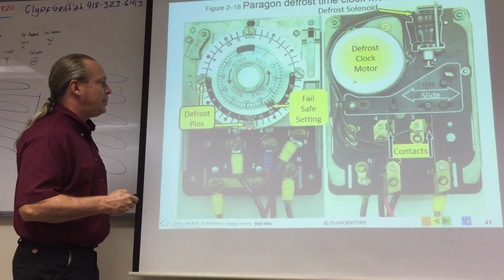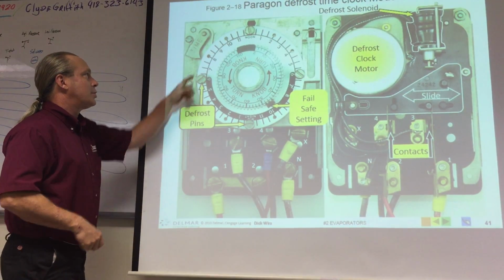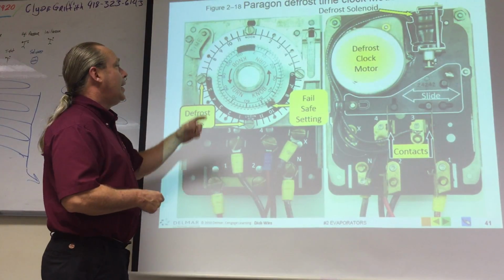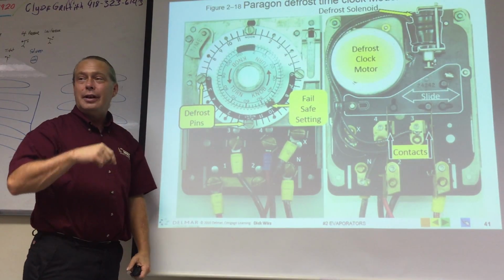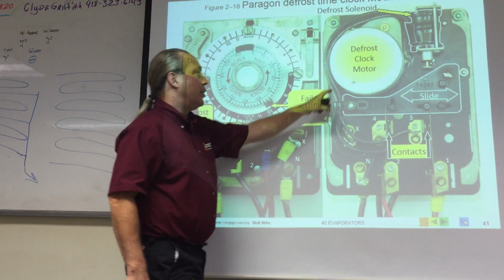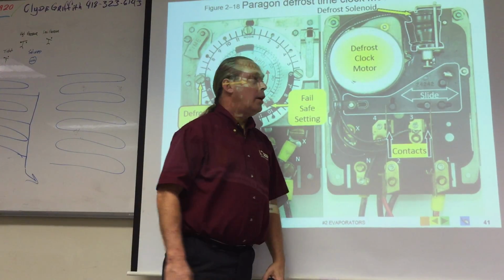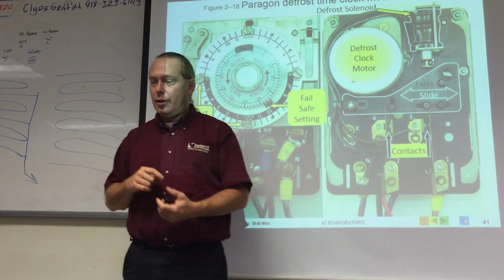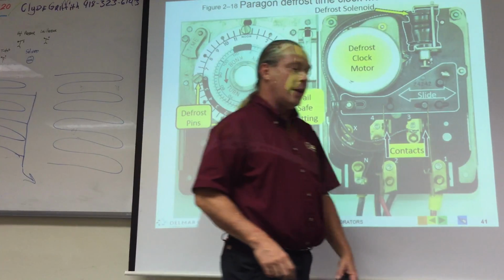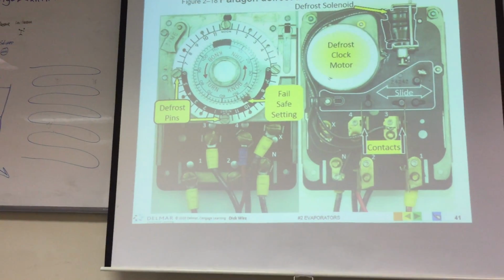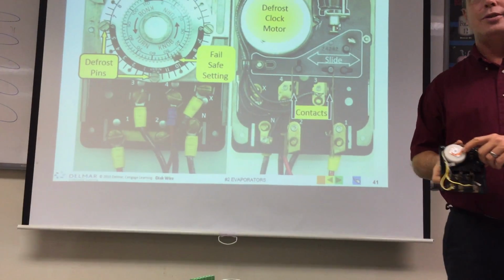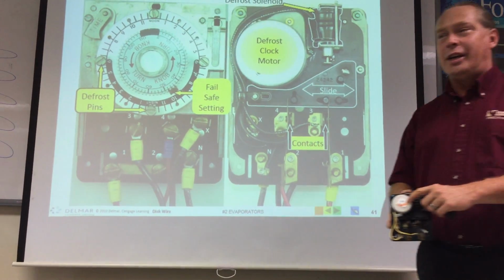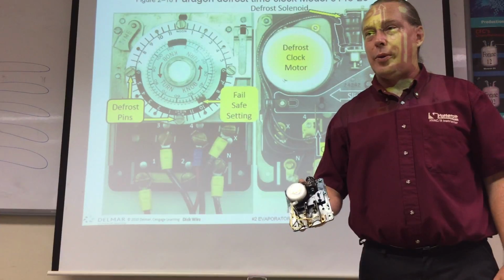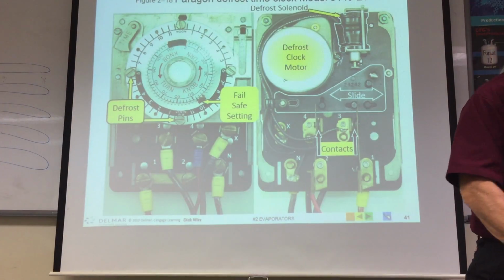Here's our defrost pins. There's just little screws that go through there, and it trips an armature as it goes by. Our defrost clock motor, a lot of those will have a little sticker on the window, especially in refrigerators. You see how this is translucent. You can see the motor running. And that's a really quick way of diagnosing a defrost clock.